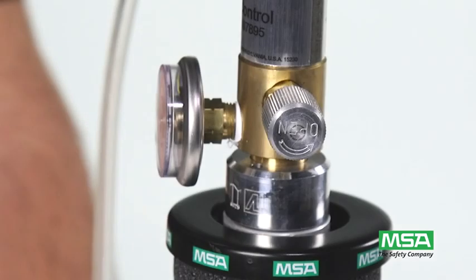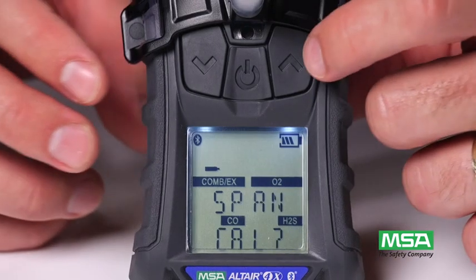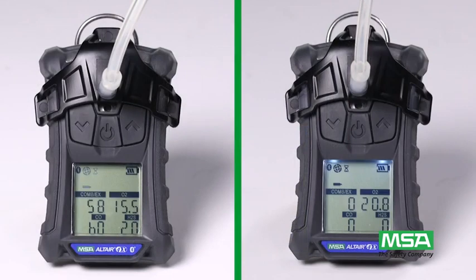After the span calibration completes, be sure to close the regulator valve. If you enter span calibration by mistake, press the up arrow button to abort.